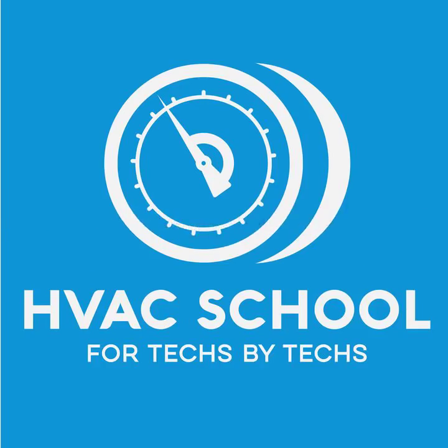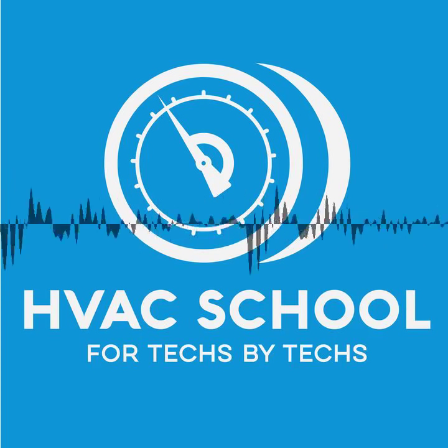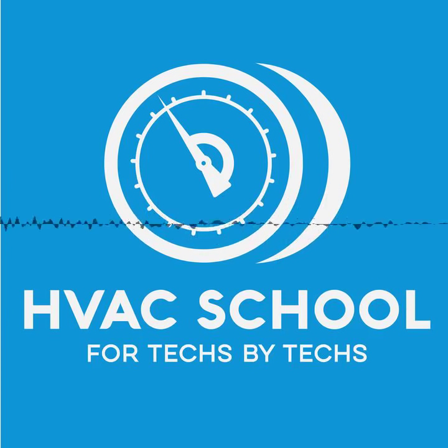Well, the other thing is that when you get a hermetic compressor or a semi-hermetic compressor, really you're buying two things. You're buying a compressor and you're buying a motor that's matched to that compressor. And the match of the motor and the compressor depends very much on what you're going to ask it to do. So a compressor that's designed for a freezer, for example, really needs a different match than a compressor that's designed for an air conditioner. And that's another challenge with heat pumps, because you really are asking it to do both things. That was one of the challenges in designing reliable heat pumps, is getting a compressor that could operate happily across those wide evaporator temperature ranges.